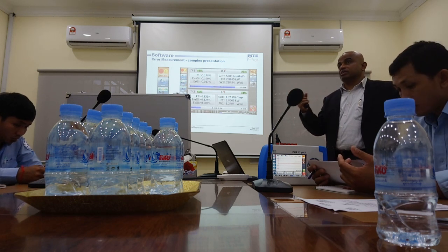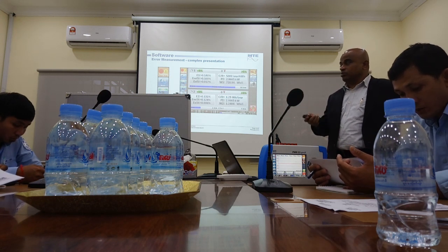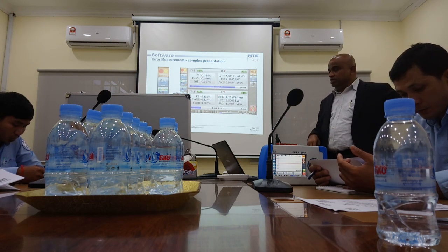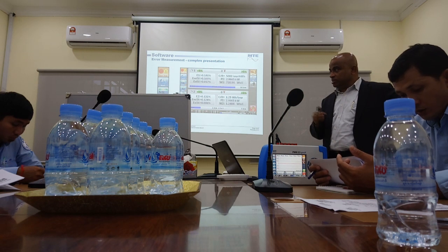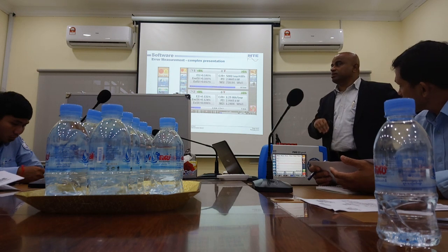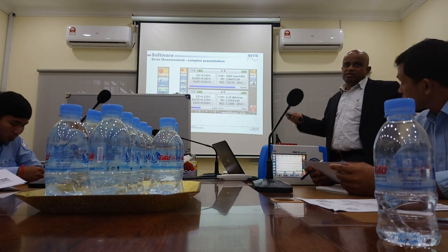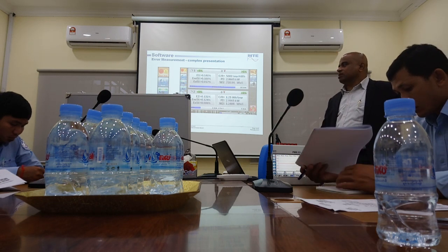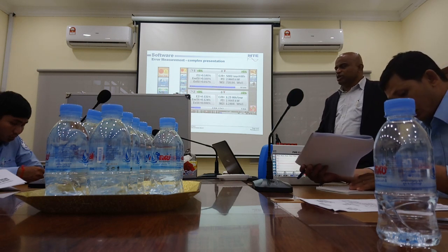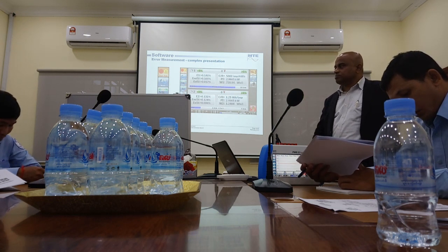Maybe in the laboratory the readings are very stable. You put it in the field, the reading is not stable. So how do you test all these things? You need to observe all these values. Is it fluctuating too much? Then you think why it is fluctuating, and whether maybe you need to do more averaging to get a stable reading, etc. So I normally keep either three pulses or something. You can even do one, but with one sometimes the reading is not so stable.